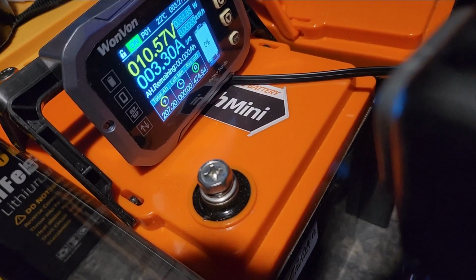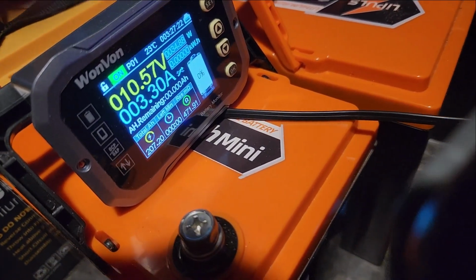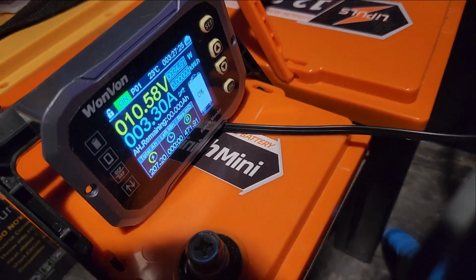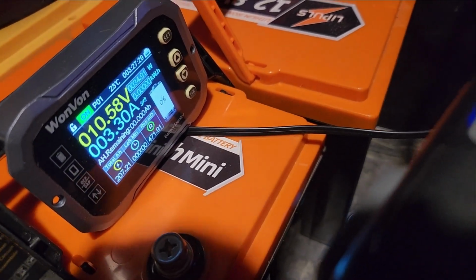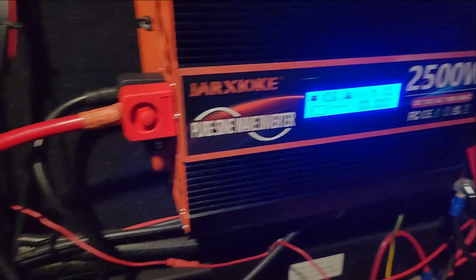So there you go, the battery put out 207 amp hours. But the battery didn't actually shut down - the inverter shut down. The battery actually supplied over 200 amp hours, 207.2 amp hours to be exact. Again, the battery didn't shut down; the inverter did, due to the voltage dropping down to about 10.4 volts. I think the battery performed very well.